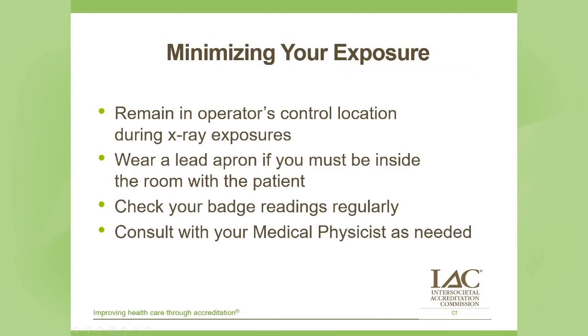To minimize your exposure, stay in the operator's control location during X-ray exposure — the medical physicist has measured the dose there and it is usually very close to zero. Wear a lead apron if you must be inside the room with the patient. Check your badge readings regularly if you are issued them, and consult with your medical physicist if you have questions.